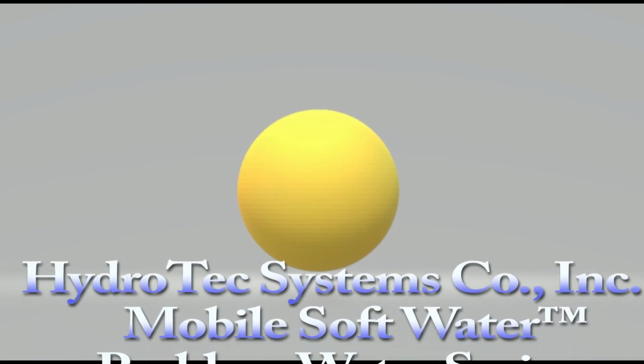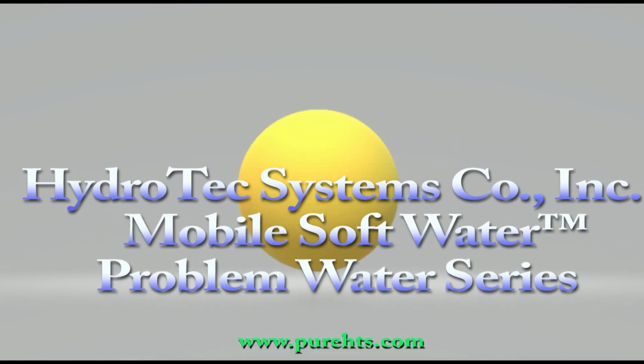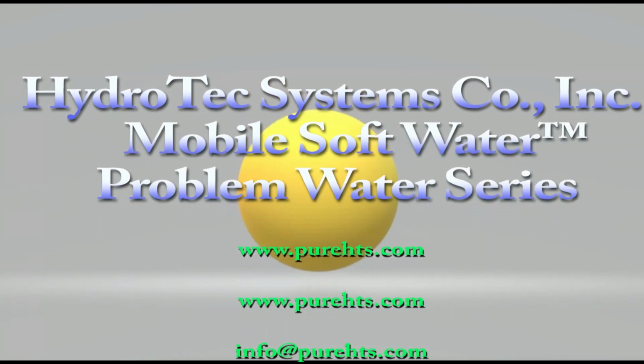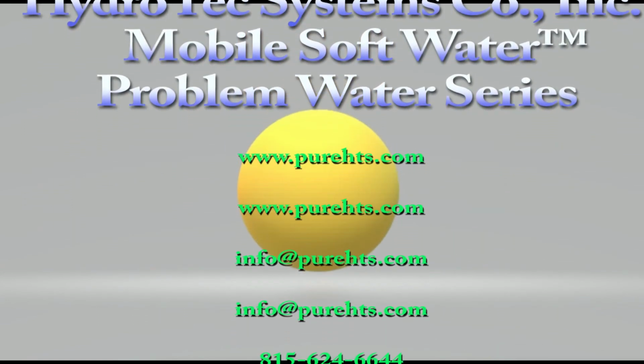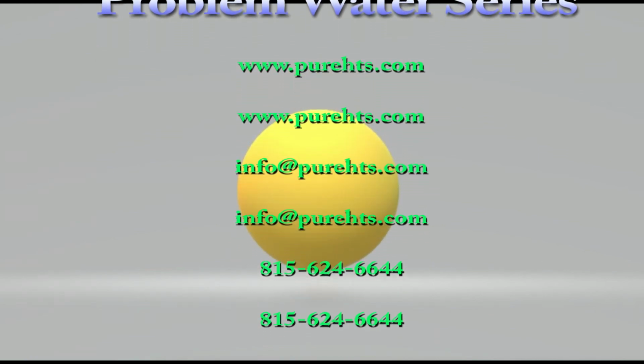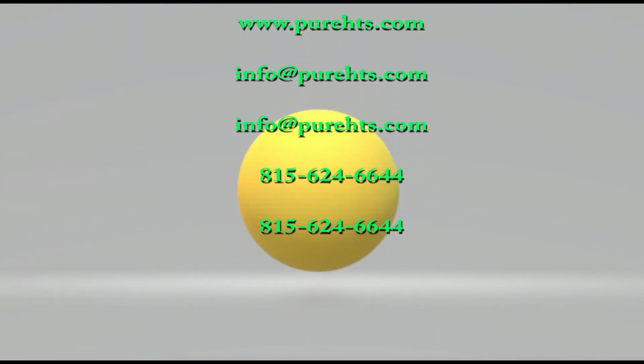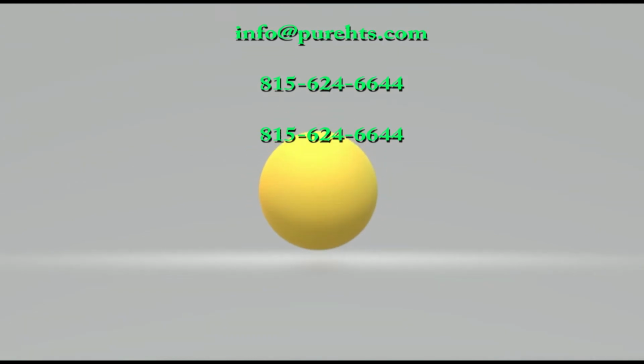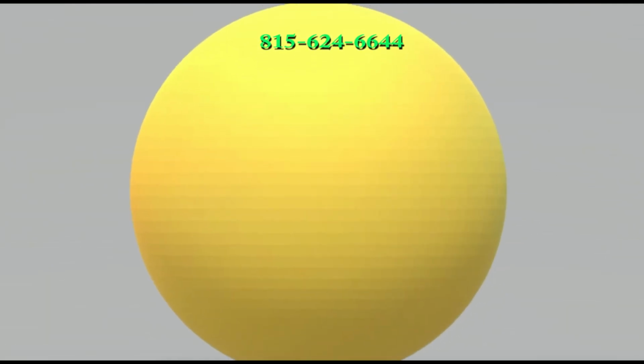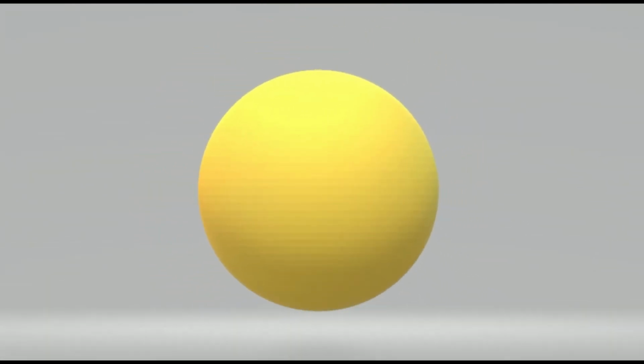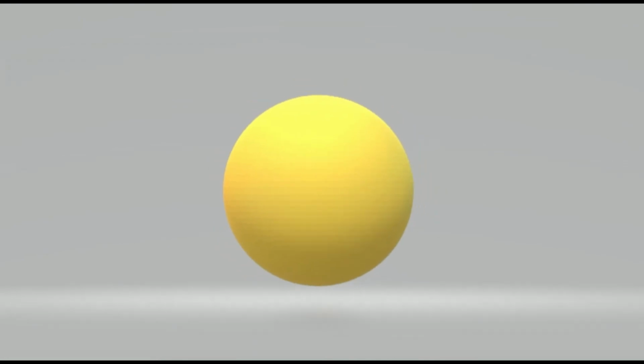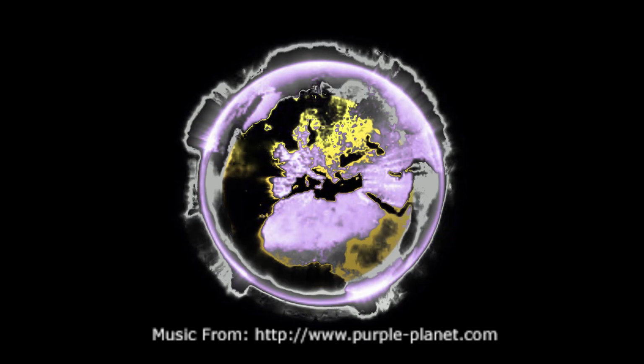In summary, damage to the resin bead cross-linkage is done by osmotic pressure created inside the resin as the water containing various concentrations of TDS increases and decreases. The change in osmotic pressure in the resin causes the plastic gelatin ball to shrink and then to expand to its normal size, only to expand larger than its normal size, then shrink back again. This is how the process of regeneration stresses your softener resin, eventually requiring replacement of that resin.